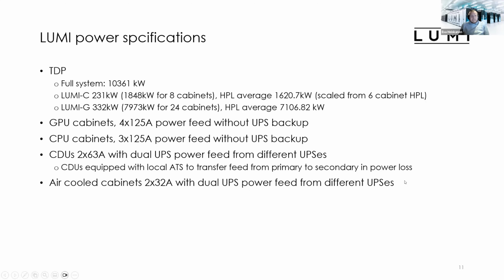Some power specifications about Lumi. Full system TDP value is a little over 10 megawatts. So our CPU partition is 231 kilowatts per cabinet. So it makes TDP value of less than 1.9 megawatts for 8 cabinets, which we currently have installed.